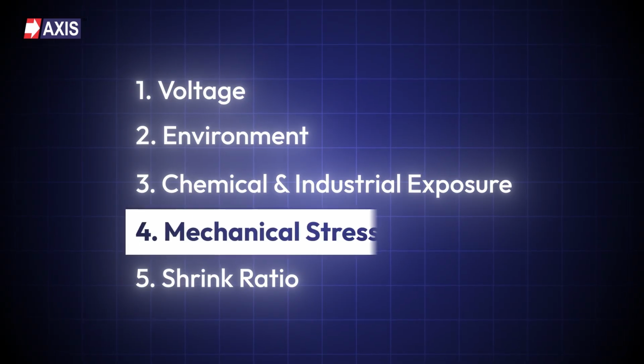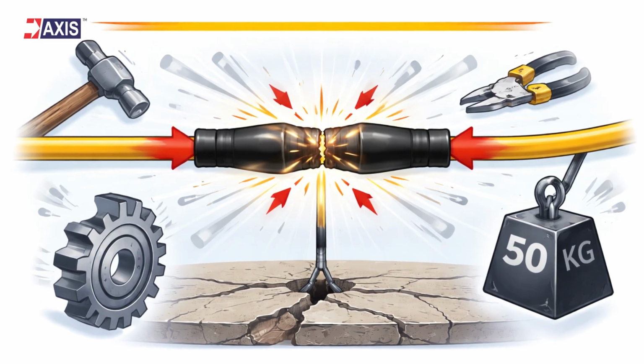Next, let's look at mechanical stress. Will your cable face abrasion or impact? If the tubing is rubbed against sharp edges or rough surfaces, thin material will wear out. Once the outer layer wears out, insulation reduces and the cable becomes exposed. Is the insulation subject to vibration? Continuous vibration can loosen tubing. Over time, this will create gaps and reduce sealing performance. Also check if strain relief is required. At jointing points, the cable may experience pulling force. If the tubing cannot support that load, the joint will weaken. Therefore, you must select the right wall type and mechanical strength based on the insulation condition.